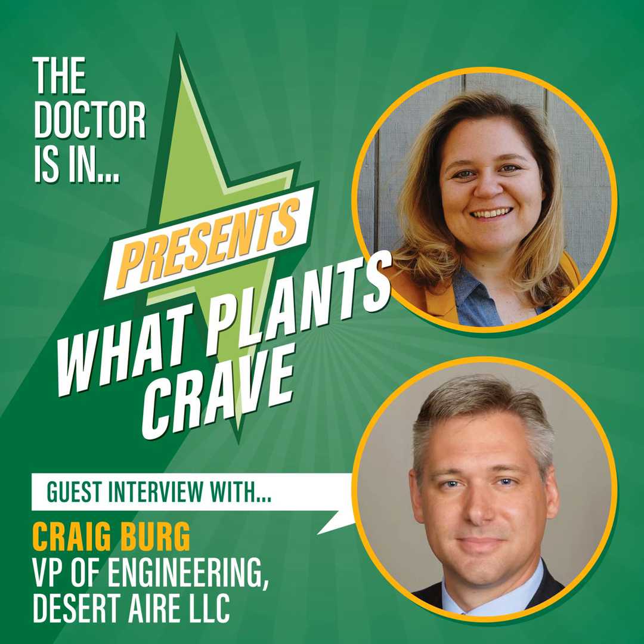Compressors, for example, I'll pick on scroll compressors: they're okay with a little bit of liquid refrigerant, but we can't compress liquid. It doesn't work, we break things when we try to compress liquid. So we have to look and say, do we have an expansion valve problem? If that expansion valve is feeding too much liquid, and it comes out of the evaporator as liquid, we can put some safeties in there, like suction accumulators, which is common. But if we put enough liquid in there, that's going to break a compressor. So getting ahead of that problem and confirming our expansion device is responding appropriately is absolutely critical. If we can cut that off before it becomes a problem, we're in much better shape.